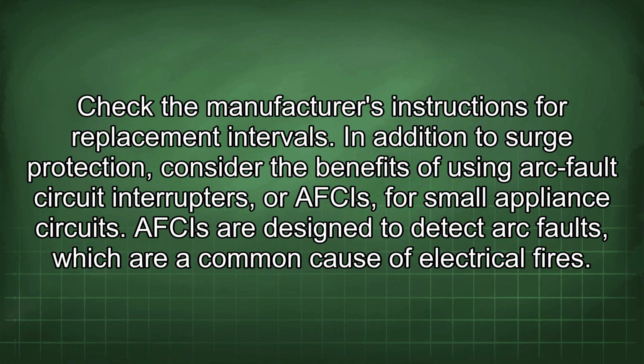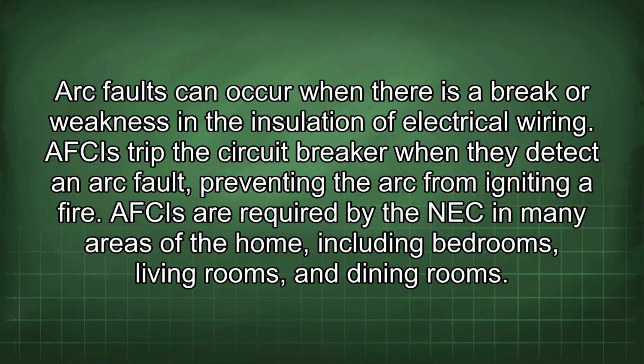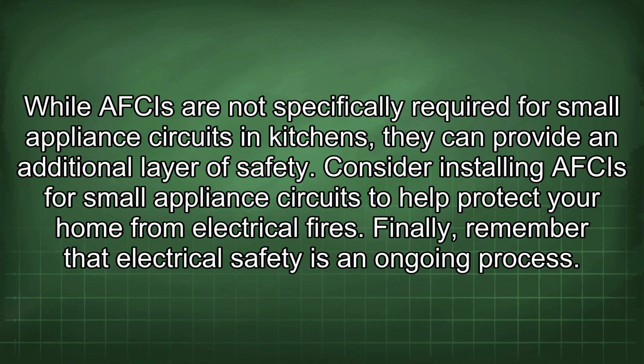In addition to surge protection, consider the benefits of using arc fault circuit interrupters, or AFCIs, for small appliance circuits. AFCIs are designed to detect arc faults, which are a common cause of electrical fires. Arc faults can occur when there is a break or weakness in the insulation of electrical wiring. AFCIs trip the circuit breaker when they detect an arc fault, preventing the arc from igniting a fire. AFCIs are required by the NEC in many areas of the home, including bedrooms, living rooms, and dining rooms. While AFCIs are not specifically required for small appliance circuits in kitchens, they can provide an additional layer of safety. Consider installing AFCIs for small appliance circuits to help protect your home from electrical fires.